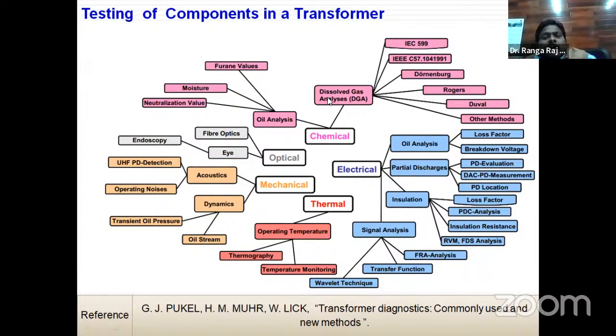So those tests are related to chemical tests. Similarly, there are electrical stress tests - we can find the breakdown voltage. A good insulating oil or paper has higher dielectric strength. Breakdown voltage is nothing but dielectric. Similarly, loss factor, insulation resistance - we can also do spectral analysis, Fourier infrared spectral analysis, wavelet techniques.